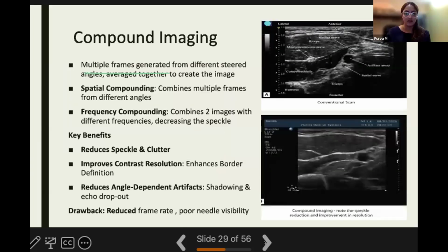Now, compound imaging. This is also a function which you can manually turn on and off in certain ultrasound machines, but in ours, in the Sonosite, it's already turned on automatically. So, compound imaging means that the machine is not looking at any one tissue or any one structure from only one direction. But what it does is it looks at every structure from multiple different directions, and then it averages all of these images that are being formed from multiple directions into one single image.